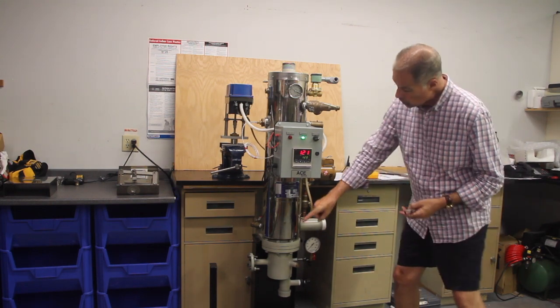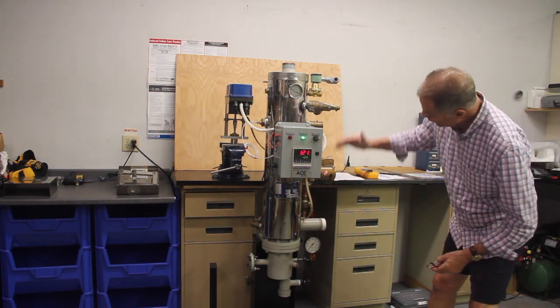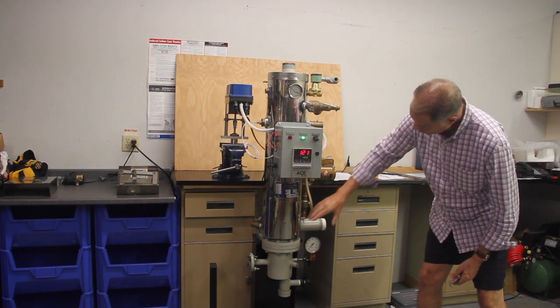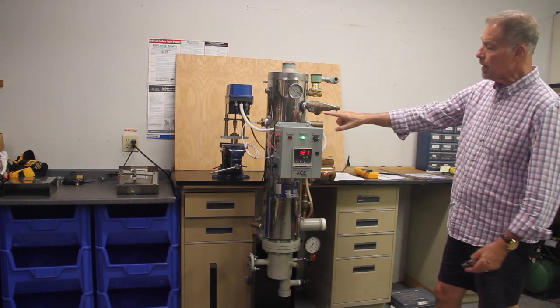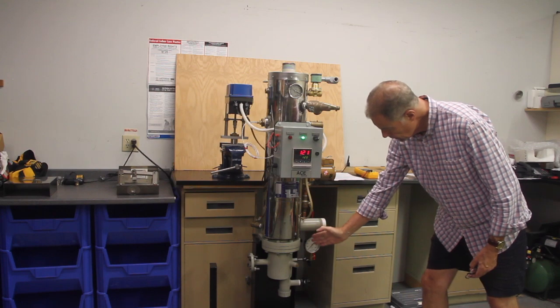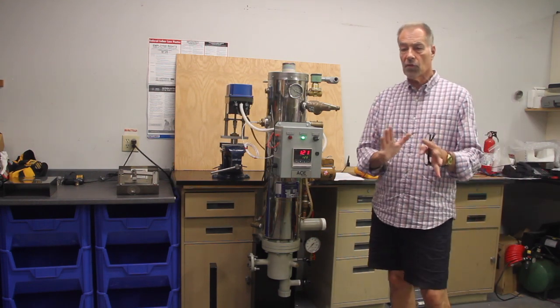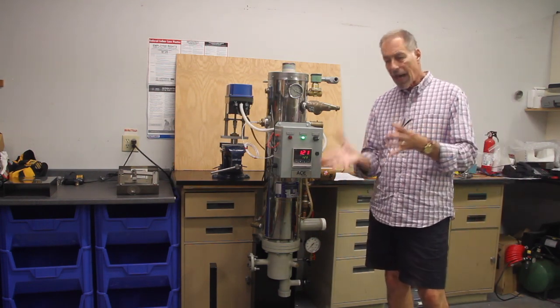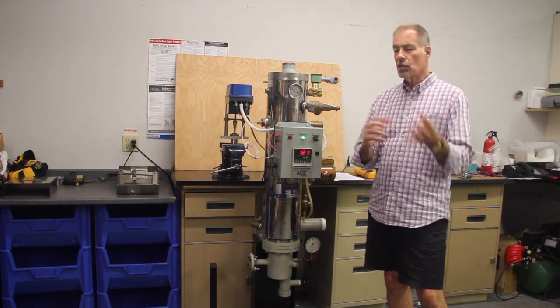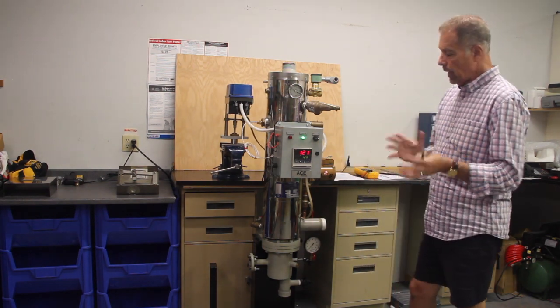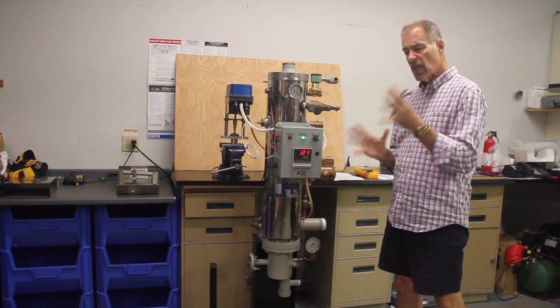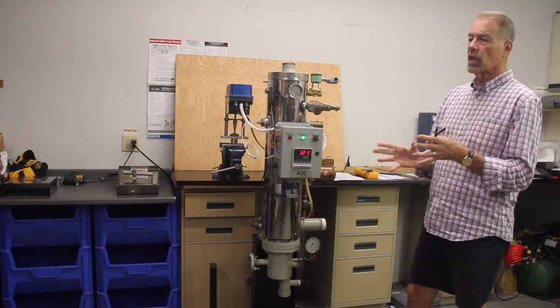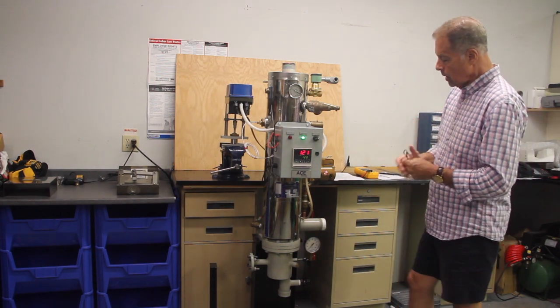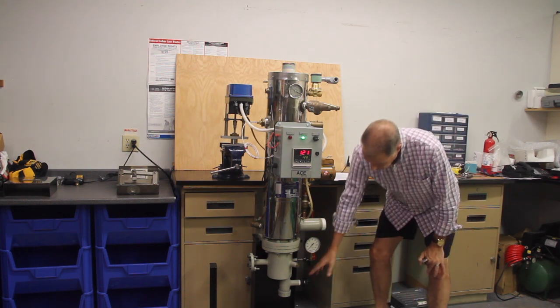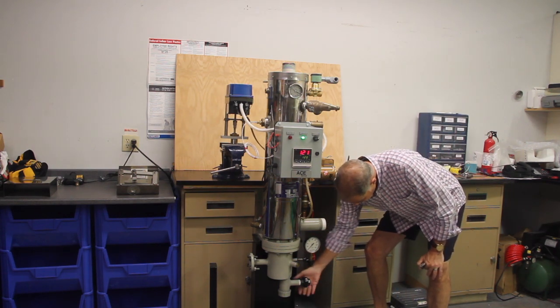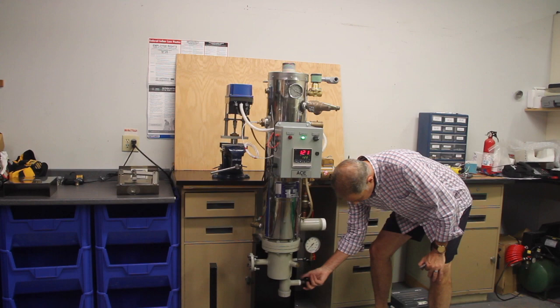So basically you have a U-tube. You've got a picture of a U-tube bundle that comes up to about here. So the first pass is steam. The back pass is what they call two-phase flow. It's steam, it's condensate, it's very hot condensate, it's flashing the steam, and it's two-phase. It's steam, poor quality steam, and high temperature condensate.